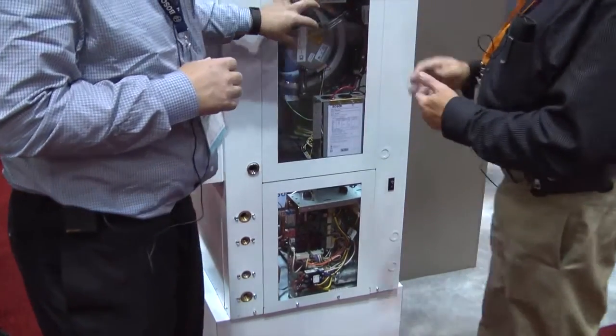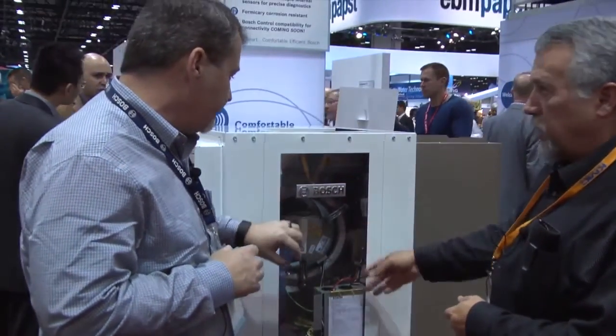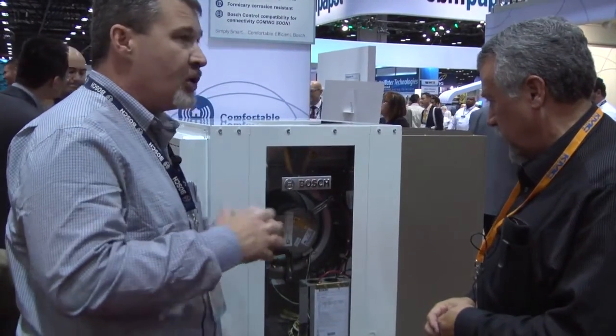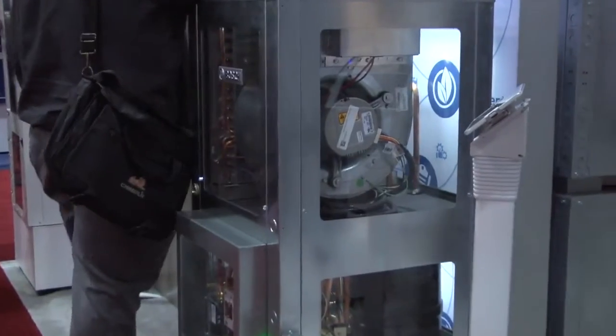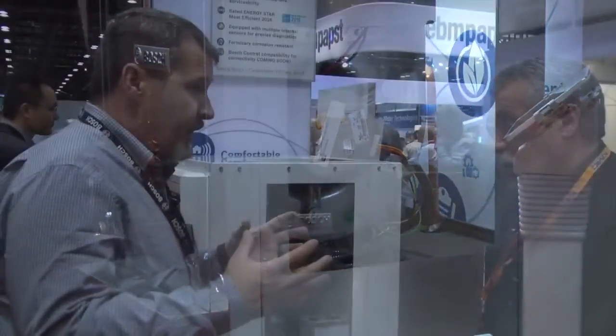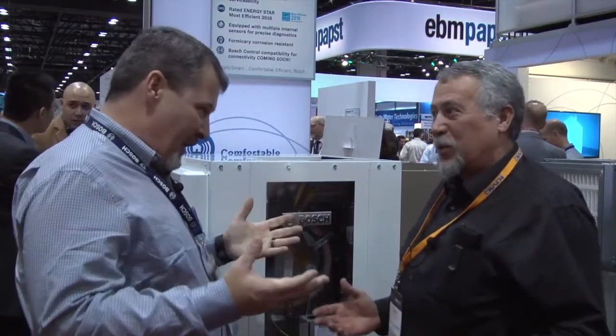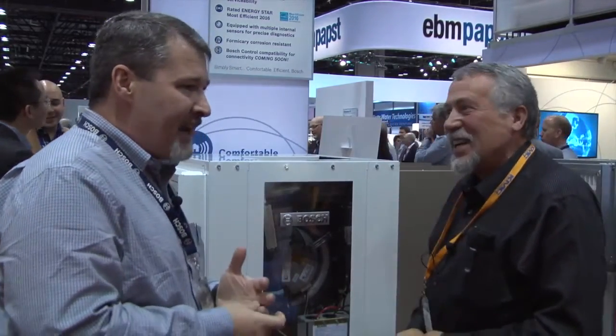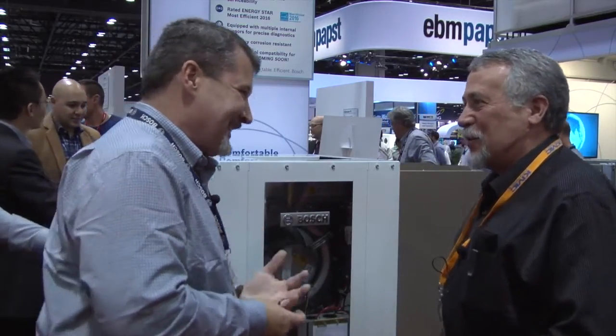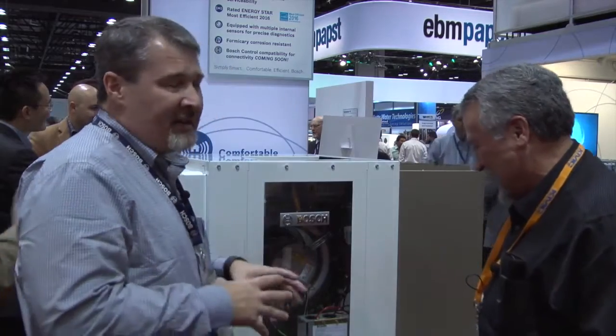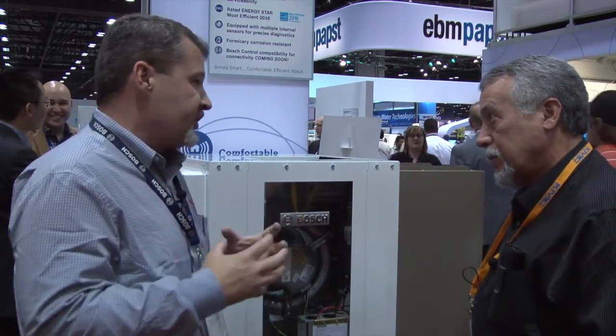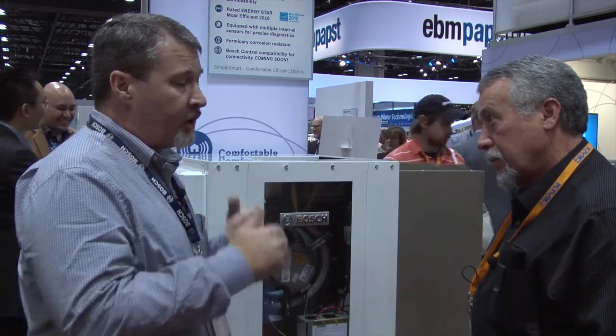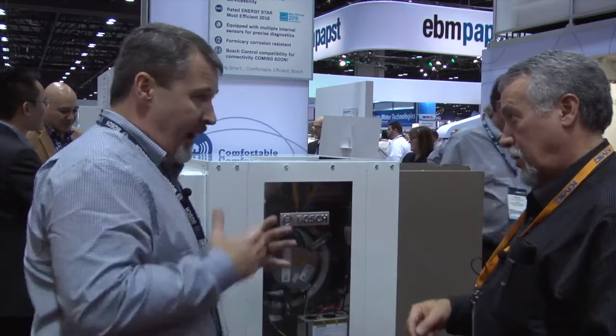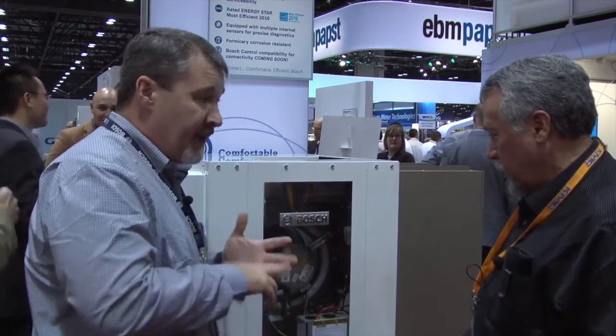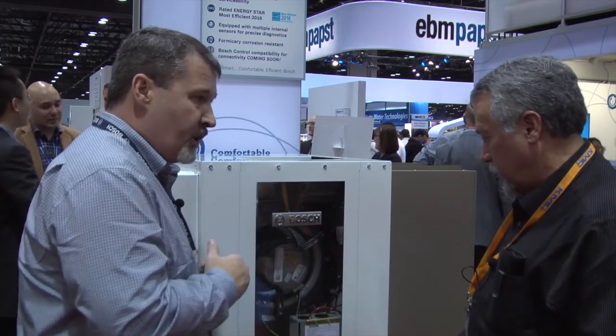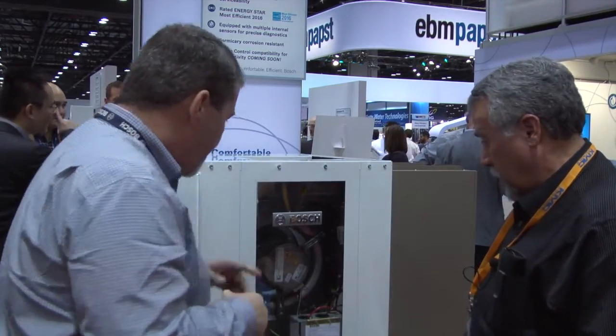So we can change CFMs on the motor up here from that circuit board. So ECM motor, obviously. ECM motor, we can actually change the CFMs to accommodate for additional ductwork, or maybe the ductwork is not perfect. And maybe the original installer didn't follow Manual D in the process? Absolutely. You'd hate to think that it happens, but I've never seen that out in the field. Yeah, absolutely. So we've given that opportunity to either ramp the motor up higher than what will be the 400 CFMs per ton standard, or if we need to do a little bit more dehumidification, our contractors can ramp that down and slow the motor down in heating and in cooling to either get a higher delta T or have more latent removal.